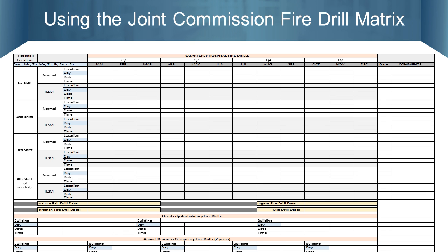I would recommend you, again, download this document and use it to record where your fire drills are or took place. What they're looking for is the location, of course, the day of the week, and the date and time. They want to make sure that you are not holding all of your third shift drills at 6 o'clock in the morning. It needs to be spread out over that third shift, for instance.